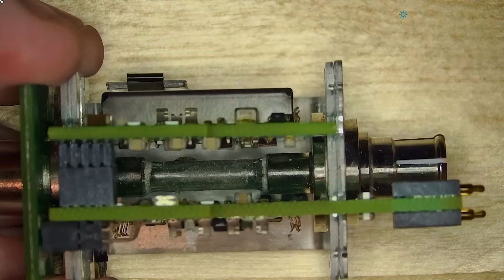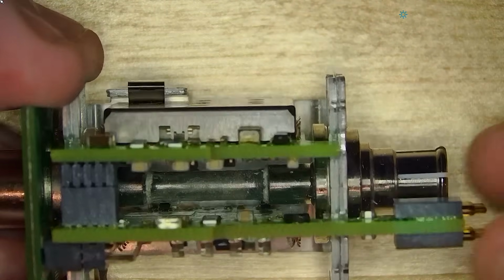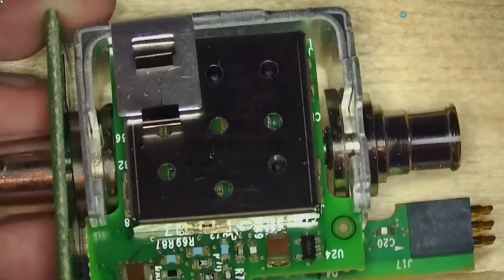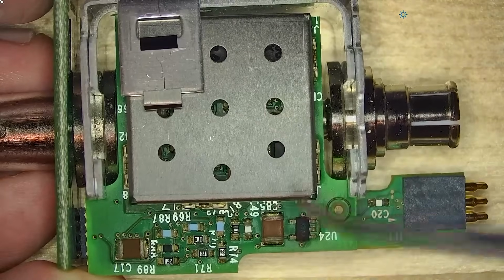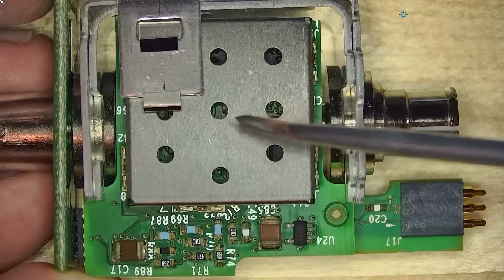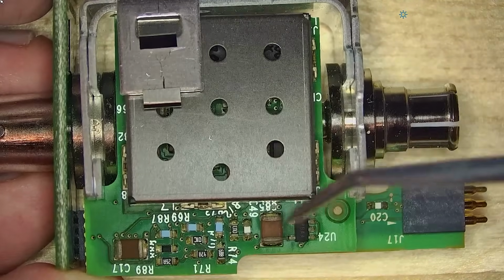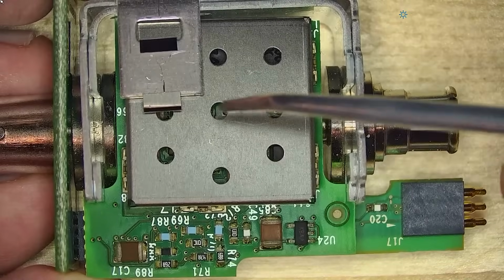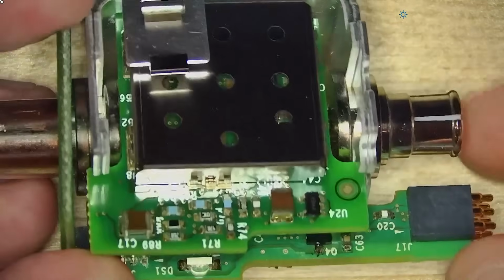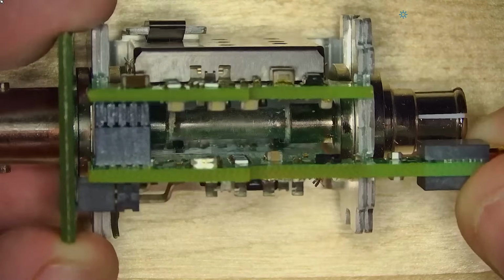Now in the middle, we don't do anything to the analog signal. As to be expected, it goes right through because you don't really want to touch that anyway. That's coming from the probe. On this side, this board is our DC-DC converter. There are in fact four in here. They have to generate plus 5, minus 5, and plus and minus 15. Each of those are then followed by a linear regulator to create a cleaner signal that you can pass to the probe. So there's a lot going on here.